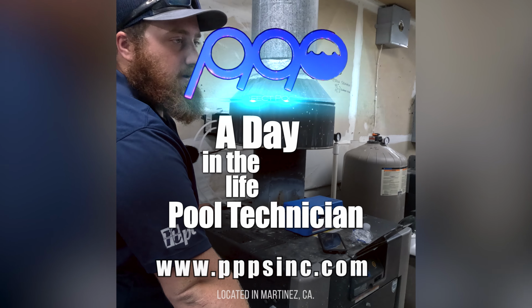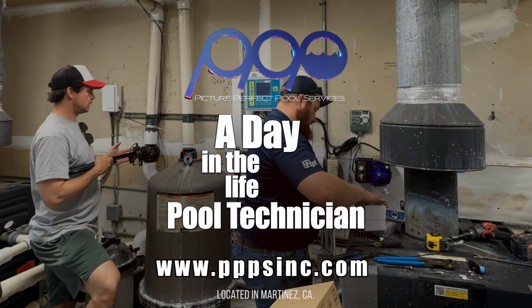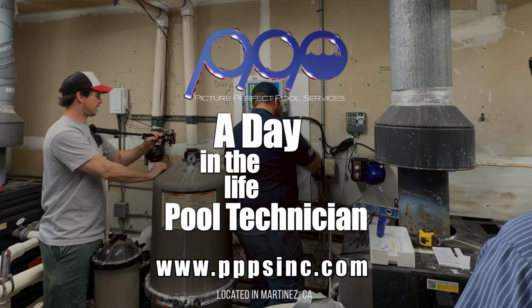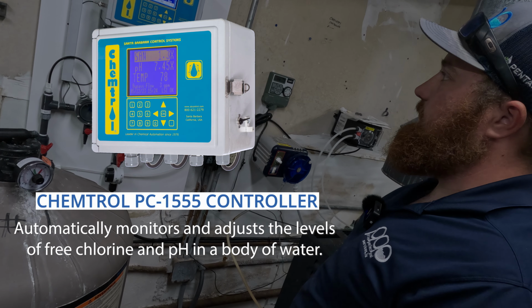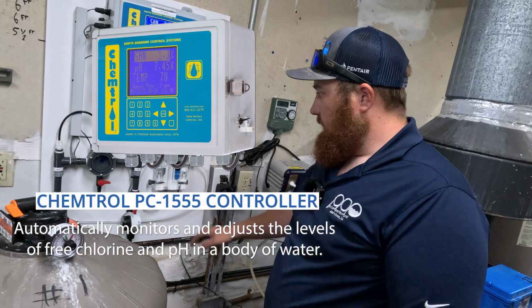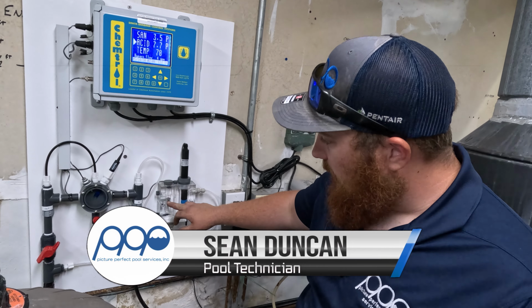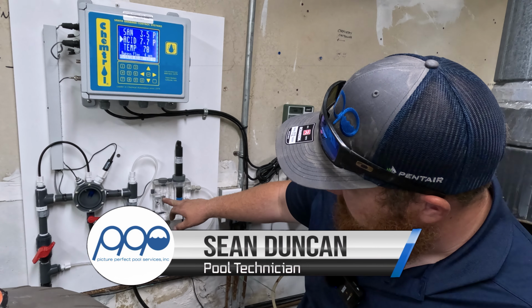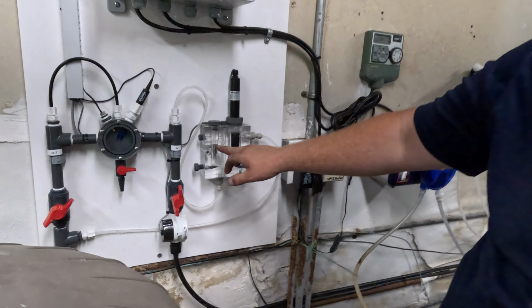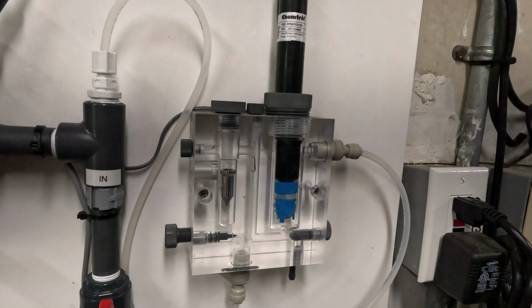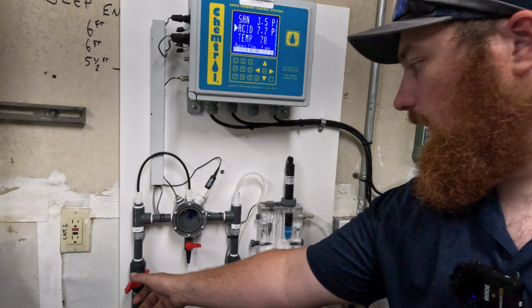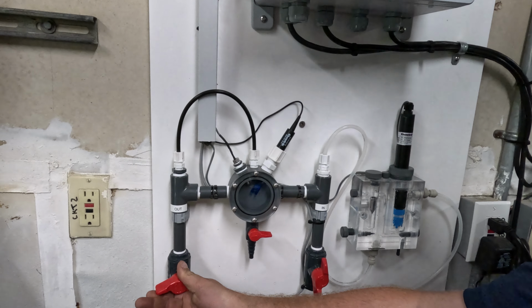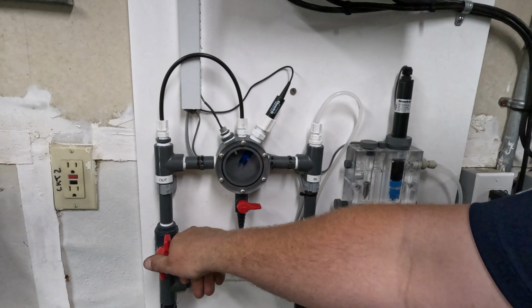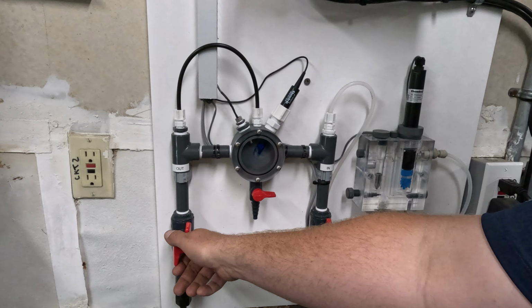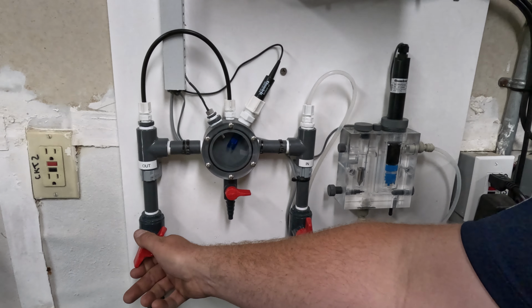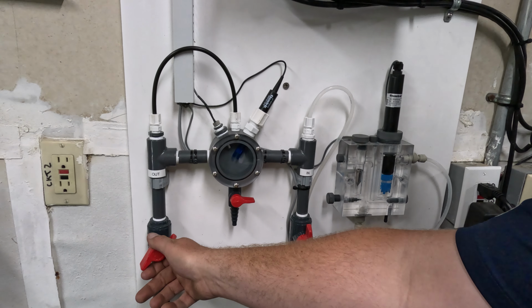Dilutes everything. So, all right, let's go over, just real quick for service technicians, what to look for on this particular controller. Go over some highlights. This is the free chlorine probe. It has a little bobber right here. You want to keep this bobber in line with this little divot that's machined in the flow cell. To control the flow going through this block, you just close the outlet valve. The more you close it, the higher it's going to go. The more you open it, the lower it's going to drop. So you've got to cockeye this valve to get that bobber sitting right at that line.